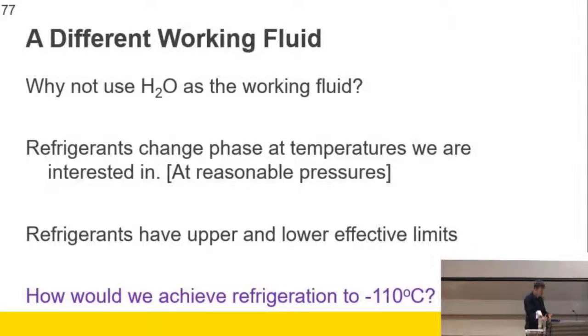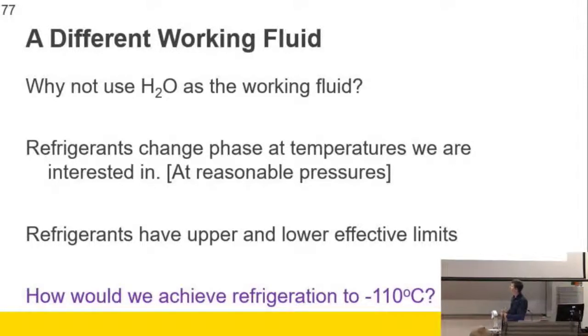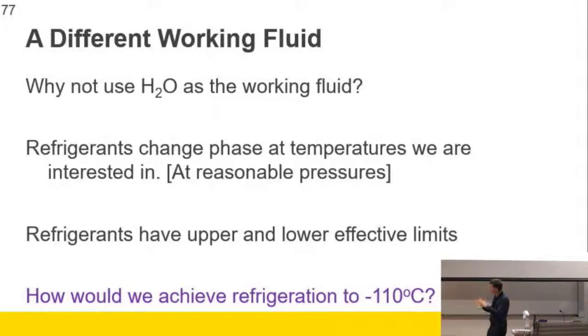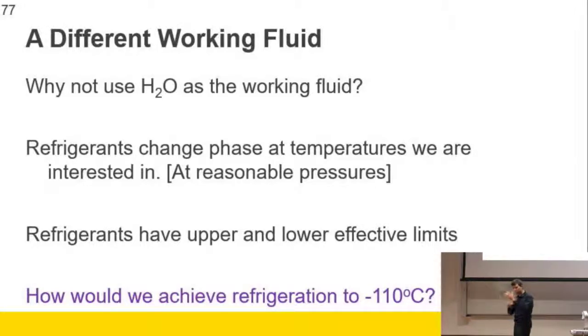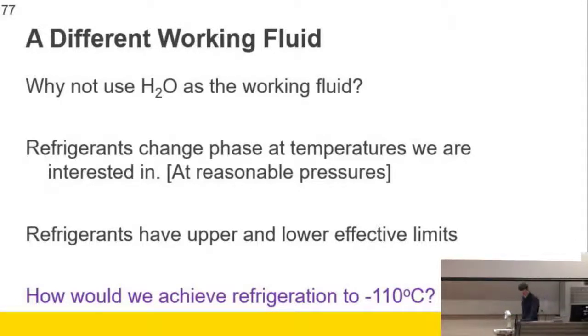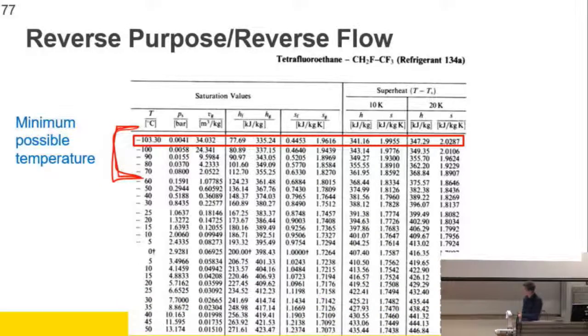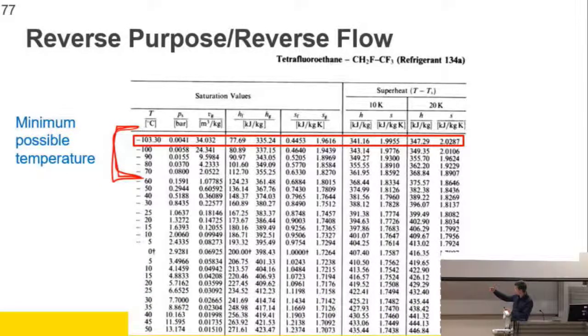You can't get water below 0.01 degrees C and still have it as a liquid. So we choose refrigerants and customize them - there are lots of them. You choose the one that will deal with the pressures and temperatures you're interested in, as they have lower and upper effective limits. R134a goes down to negative 103, although you'd more typically use it down to maybe negative 40 or negative 30.